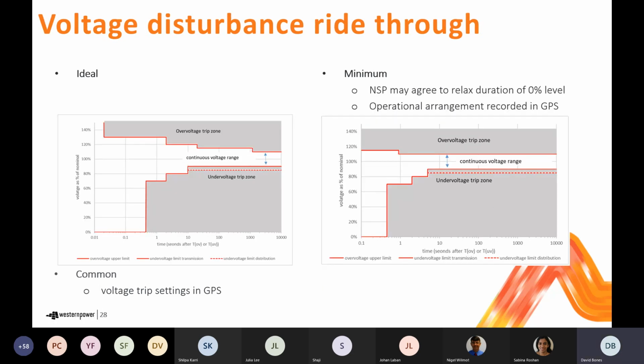So as I said, the next disturbance ride-through requirement relates to the size and duration of voltage disturbances. Again, we've got two charts on the screen illustrating the ideal on the left and the minimum on the right. You'll see on the two charts there's full red lines and dotted red lines, with the dotted red line appearing for the under voltage region. So the full red line refers to, in the over voltage region, the requirement of both the transmission and distribution level, and for the under voltage region, if you're distribution connected, then it's the dashed line that you need to adhere to. If you're transmission connected, it's a full red line.